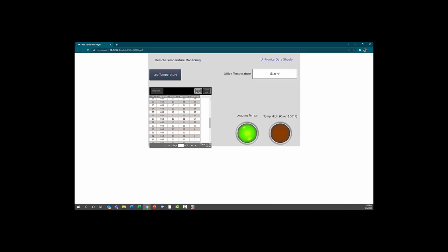Provided they have been edit enabled, like the temperature here in the web page is view only. And the editing capabilities of this data table have been turned off, just so you can have different sorts of functionality on your different locations. Like if you want someone to be able to remote connect to the PLC and edit its values, you can use VNC. But if you want another user only be able to view, that viewing can be set up with the web page while you have the VNC have all the edit enabled as if you were standing in front of the PLC.